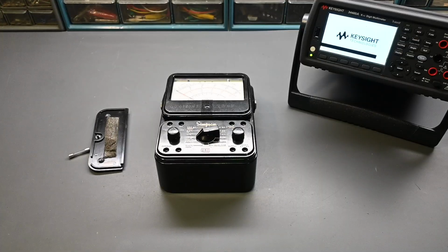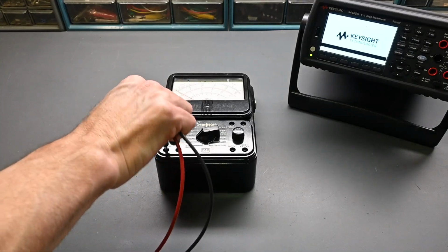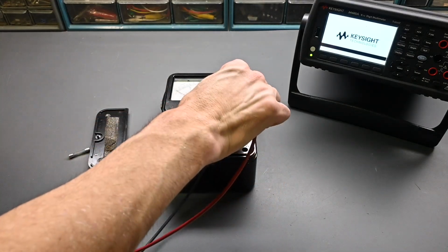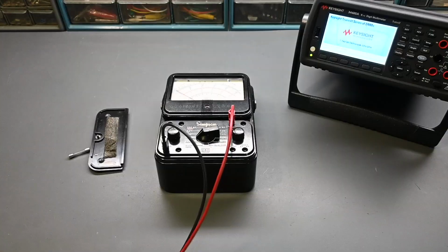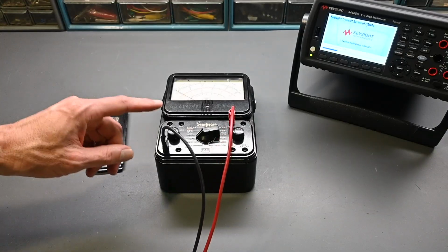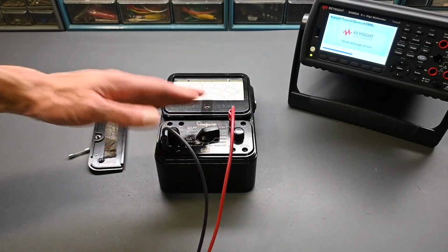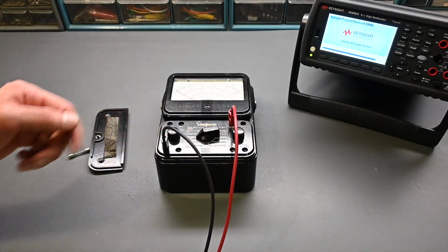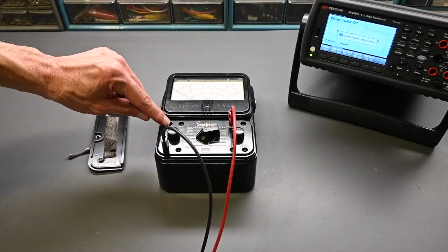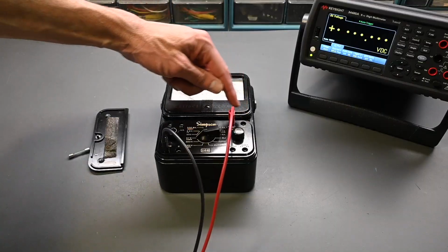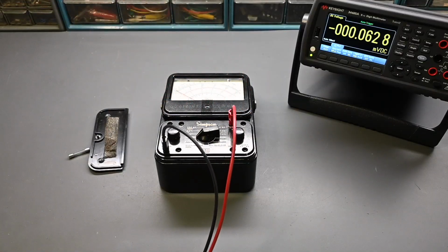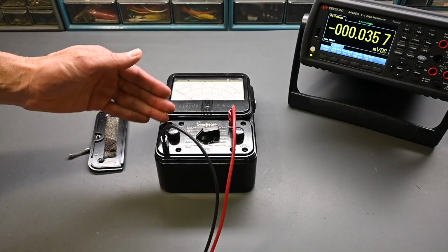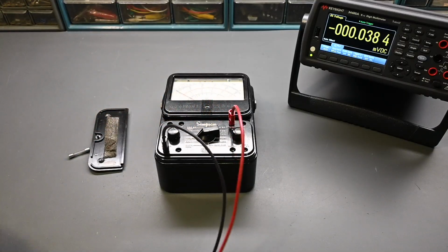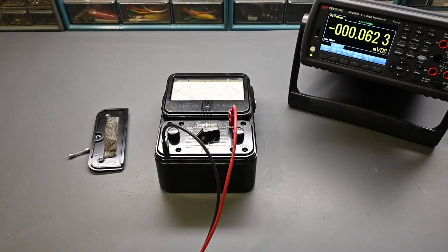I'm going to grab these test leads. That fuse we were looking at is in line with the common jack, so pretty much all the measurements you make, that fuse is always in the circuit, other than when you measure with the 10 amp. There's a minus 10 amp and a positive 10 amp jack, and there's no fusing on that 10 amp shunt, so the fuse has no protection for that higher current. But for all the other measurements, the fuse is certainly in the circuit for protection.